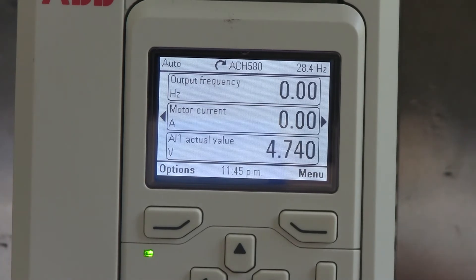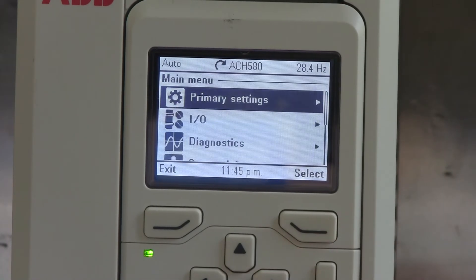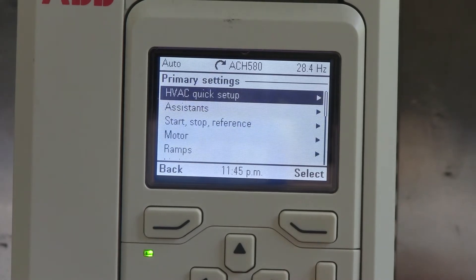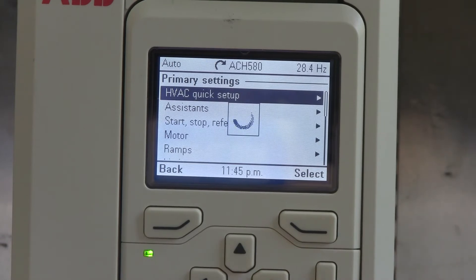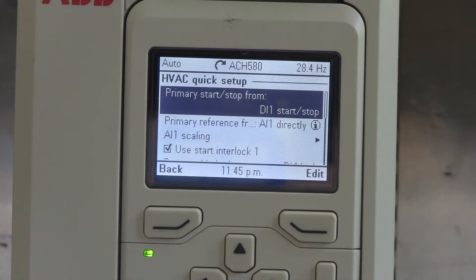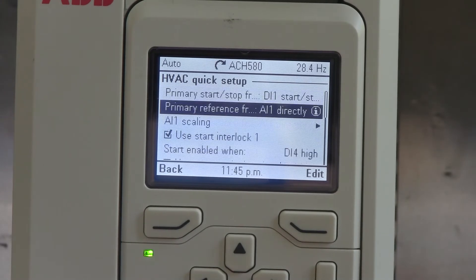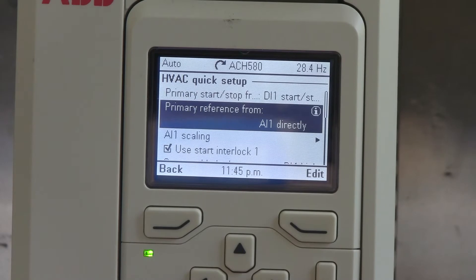The first thing you're going to have to do is hit the menu button, go to primary settings, highlight HVAC quick setup, and then it's going to ask you a series of questions. The first thing it's going to ask is where you want your start-stop — we're saying DI1, that's fine. The primary reference is from analog input number 1, and that's fine.